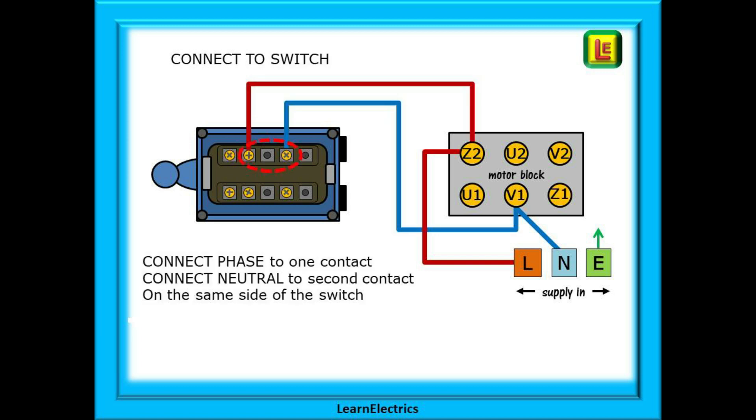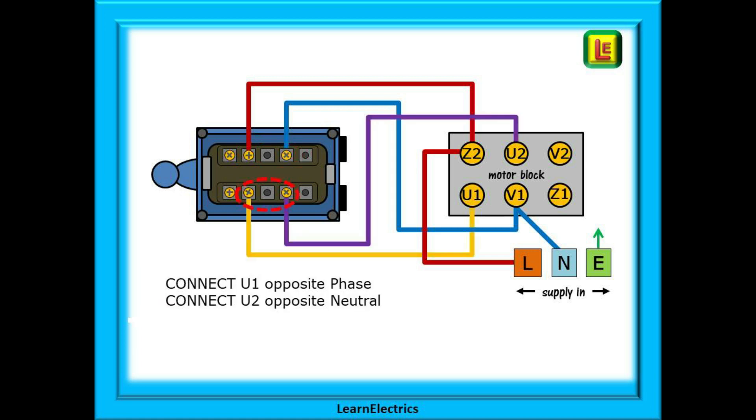Now start connecting the wires from the motor block to the switch. Connect the phase wire from Z2 to contact number three of our switch and the neutral to contact number seven. It is very important that the phase and neutral are on the same side of the switch. Now we can connect U1 on the motor block to contact four on the switch and U2 on the motor to contact number eight of the switch. U1 should be opposite the phase and U2 opposite the neutral.